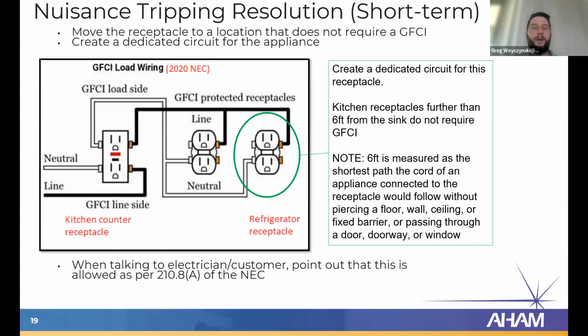One of the things you can do and recommend to an electrician as a fix is put this refrigerator on a dedicated circuit. So remove it from this branch circuit and feed wires directly from the refrigerator receptacle back to the breaker panel. In that case, it does not have to be a GFCI. So you can avoid the GFCI requirement by creating that dedicated circuit. When you're talking to an electrician, you can point out, hey, this is more work for you, and it is allowed by 210.8(A) of the NEC. So that's another short-term fix.